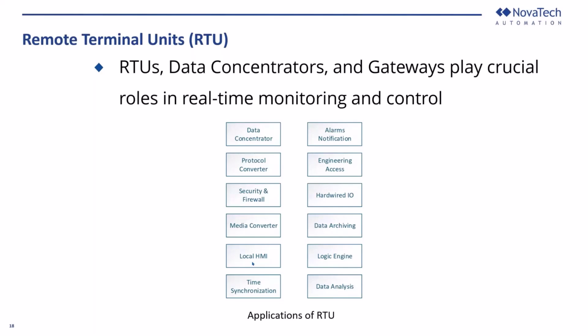They're somewhat comparable in terms of functionality, but they play a crucial role in real-time monitoring and control. We've jotted down some of the applications that an RTU can do. The data concentrator is the most important one. It interfaces with the SCADA system for remote monitoring and control, and is typically connected to all the meters, relays, and other substation equipment. So the data gets consolidated into an RTU, is concentrated, and then fed to the SCADA for visual purposes or control purposes.